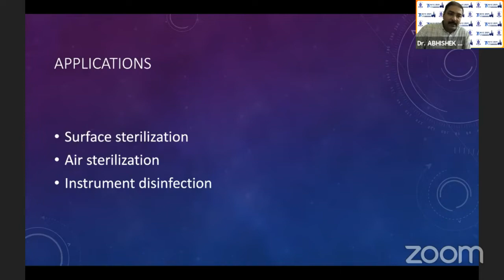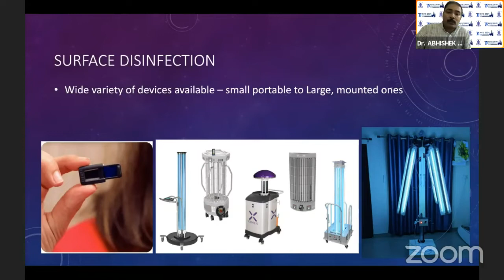Depending upon the wattage of the UV light, you can have different exposure times, but anywhere between 10 to 20 minutes is the exposure time. You can easily shift these room to room, and these will always sterilize the surfaces that are illuminated. It is not going to work in the shadow. It has no indirect effect. So you have to make sure that the supposedly contaminated area is exposed well to these lights.